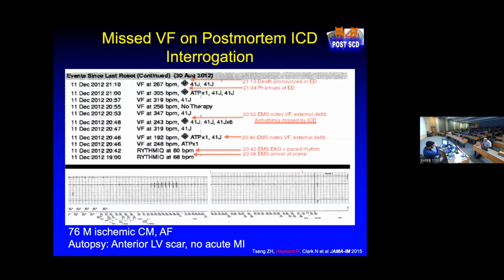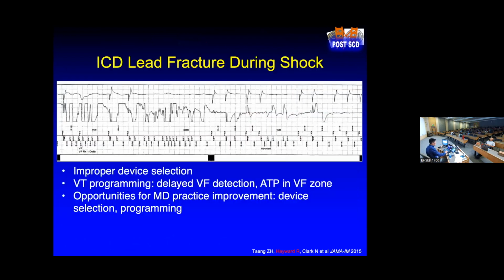And that's exactly what we saw. So here's an example of ventricular fibrillation. I'm not going to walk you through everything here, but suffice it to say, ventricular fibrillation in this defibrillator case was missed, only seen looking at the postmortem interrogation. It was undersensed by the device, and paramedics had to shock externally. If we line up the EMS run sheet with this defibrillator interrogation, there are episodes of VF that were completely missed by the device. That's why this person died suddenly, because the device undersensed VF. So even if it's not necessarily a hardware problem, software problems, or even the way we design and program devices, it can lead to undersensing.